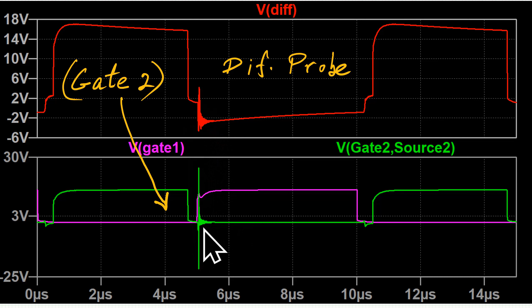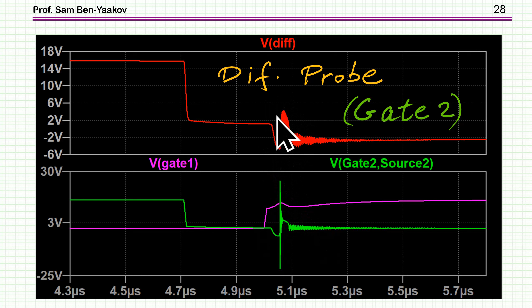First of all, it doesn't capture the very high, fast responding spike. There's no clamping here, but this is just the bandwidth. It's not enough for this sharp spike. And also you see that there's some extra oscillation, probably due to the fact that we have inductance at the input to the probe, okay? So we see that the probe can, of course, add errors in the measurement, and this is something to worry about. And here, this is an expanded scale. You see, this is the supposedly correct shape of the pulse here, and this is what you get from the probe due to the limited bandwidth and also the oscillation that it generates itself.